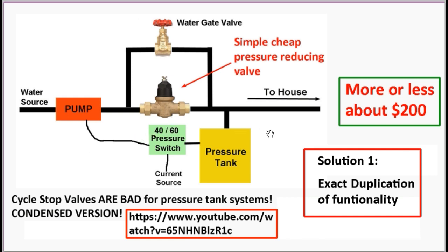So if you turn on a lot of water, this has very little effect because it only allows a tiny bit of water through. Most of the water is coming through this pressure reducing valve, which limits the pressure to 50 pounds in this example. I didn't put the 50 here, but I should have. The pressure switch is set to 40-60, and this pressure reducing valve is set at 50 pounds.